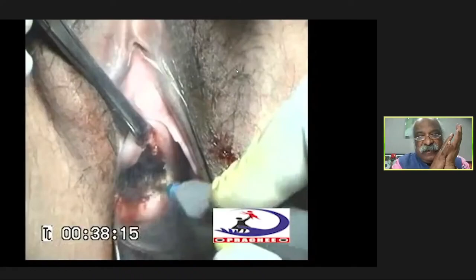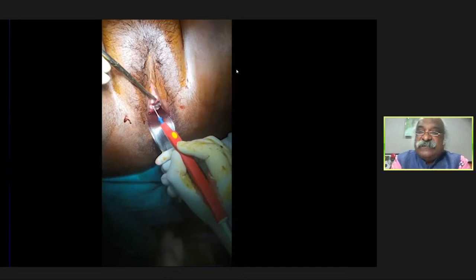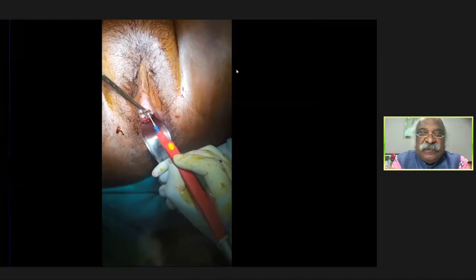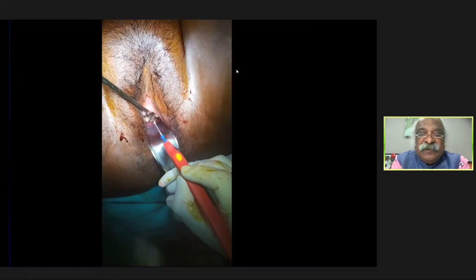You can see the sparkling current. There is a 1 to 2 millimeter gap between the electrode and the tissue, and the current sparkles. So this is a jumping current which is being adjusted by the modulator in the electrosurgical unit as a function of the spark current. And this spark current you apply so that the current is flowing at a distance, with a gap of a few millimeters from the electrode to the tissue contact.